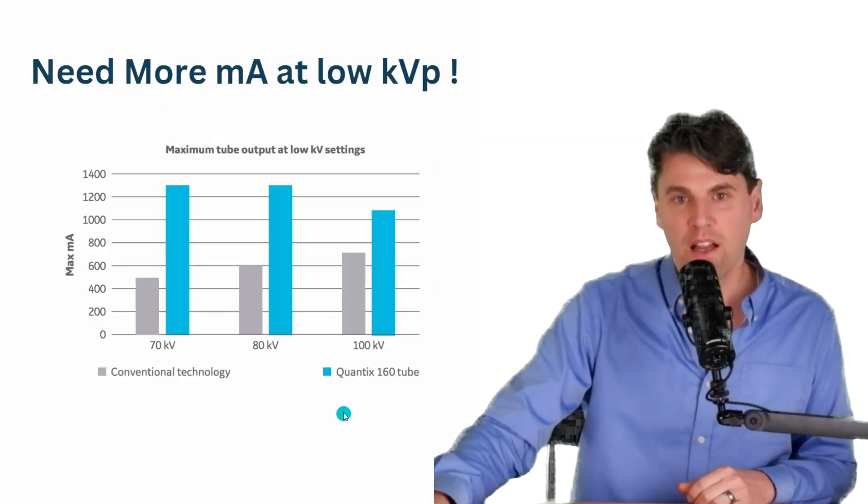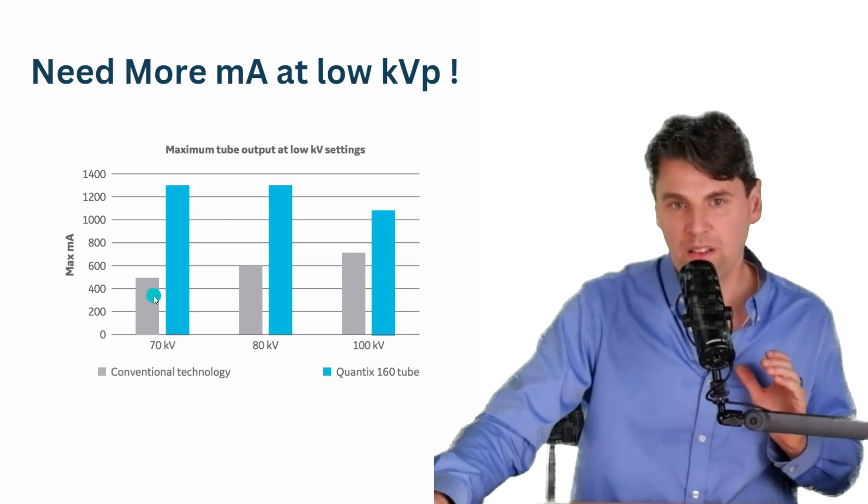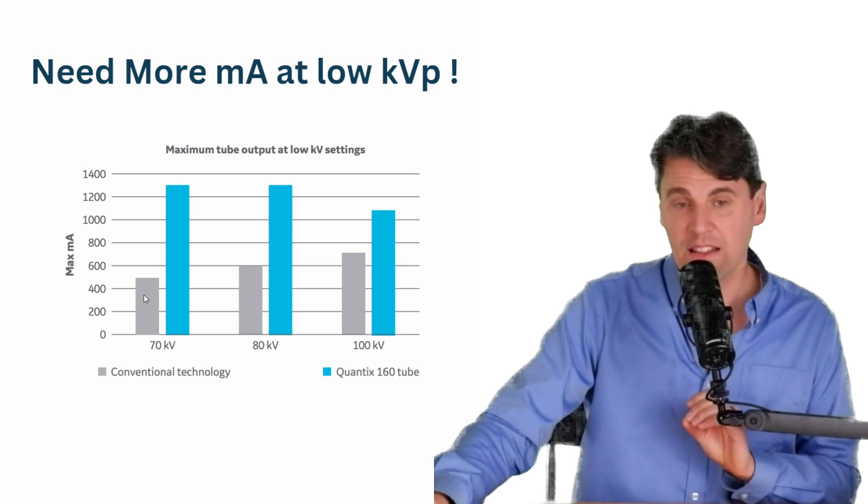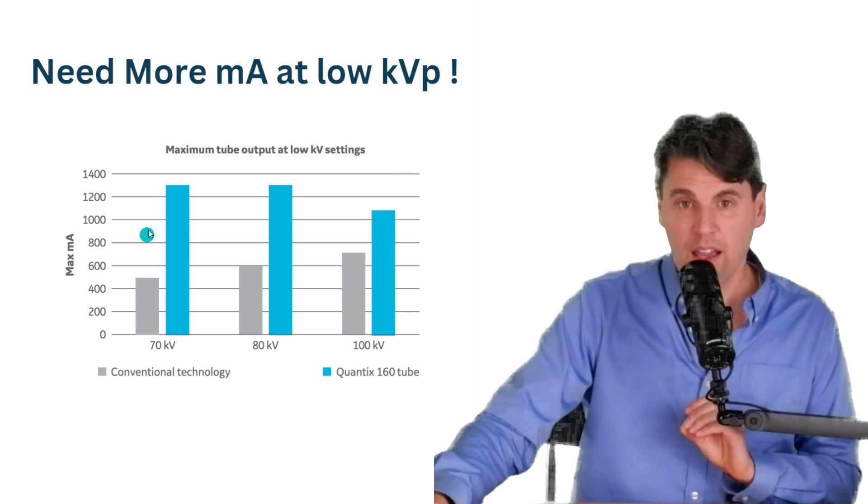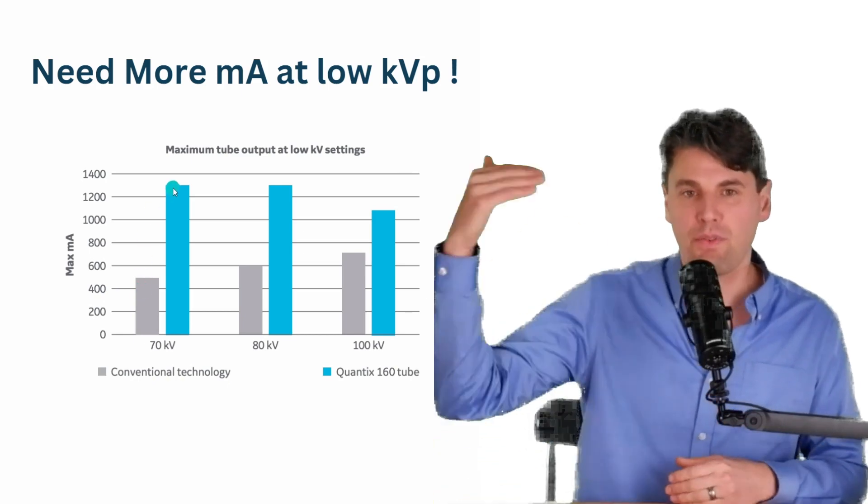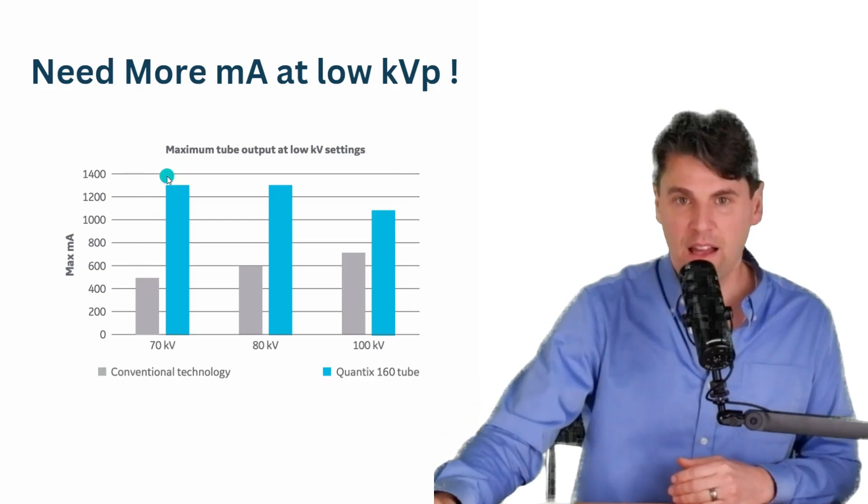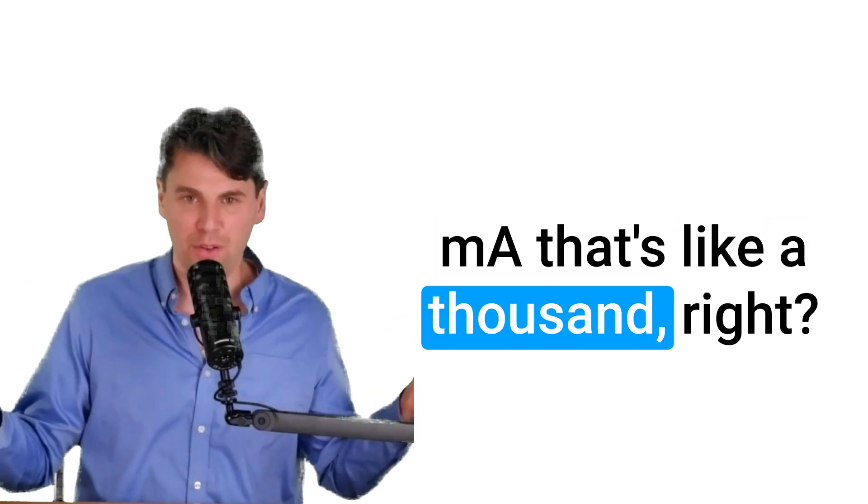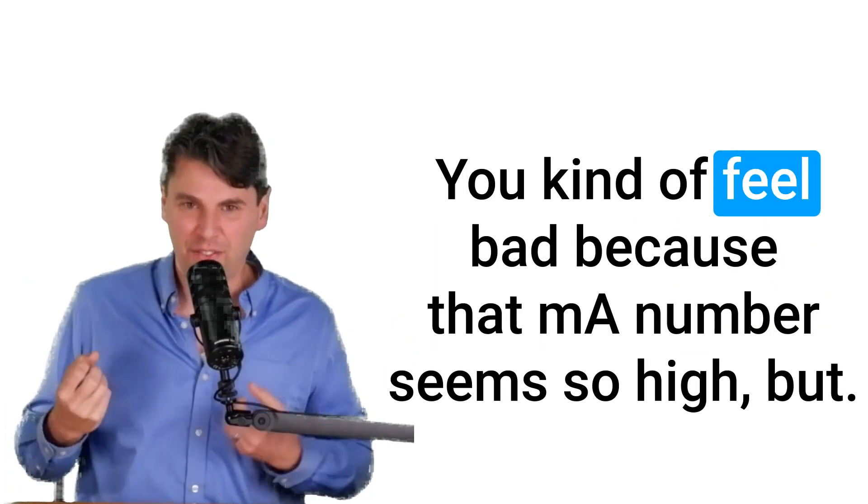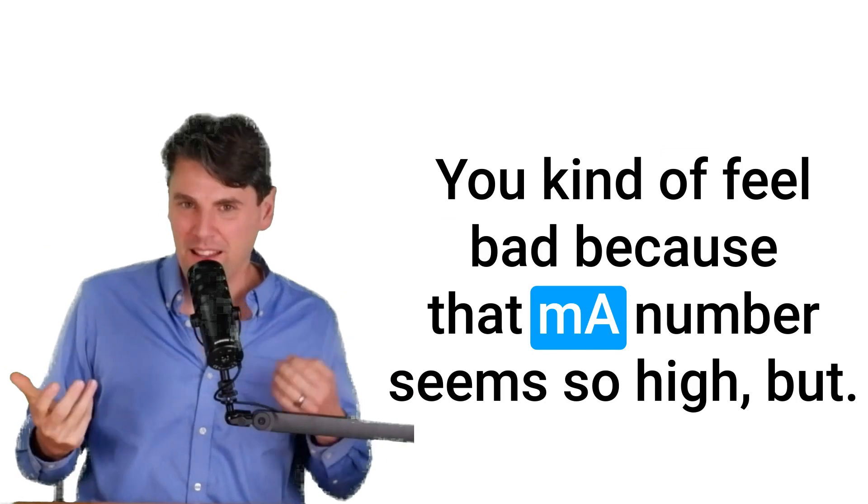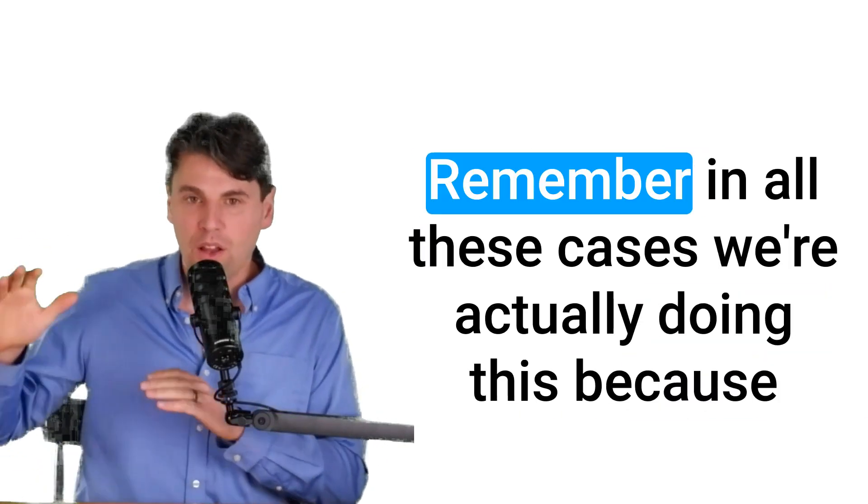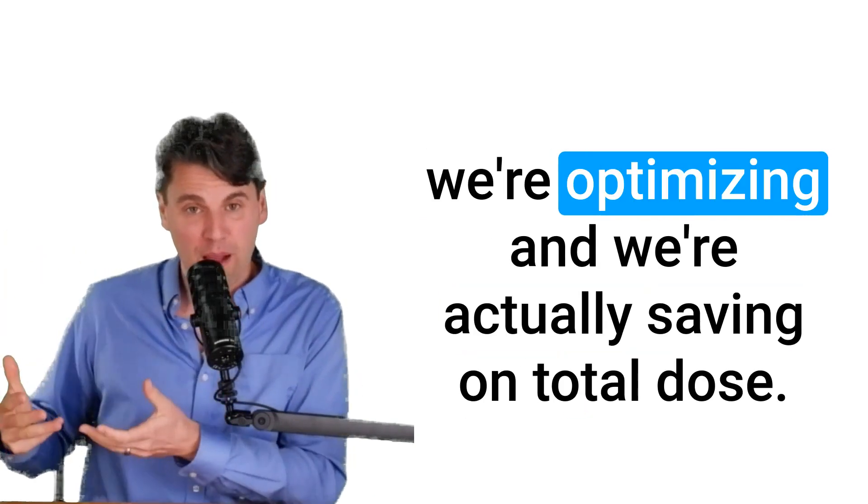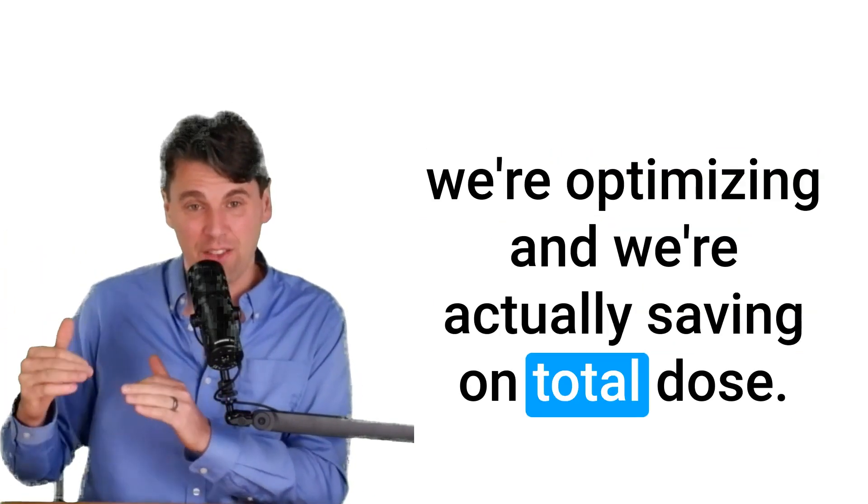So that really allows the vendors to go from relatively lower MAs that were achievable at these low KVPs and go up by several factors to really high MA levels. You don't have to be worried when you see an MA that's like a thousand, right? You kind of feel bad because that MA number seems so high. But remember, in all these cases, we're actually doing this because we're optimizing and we're actually saving on total dose.